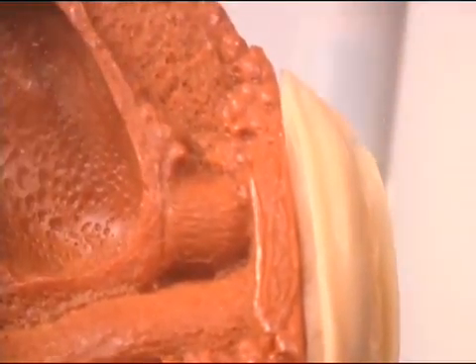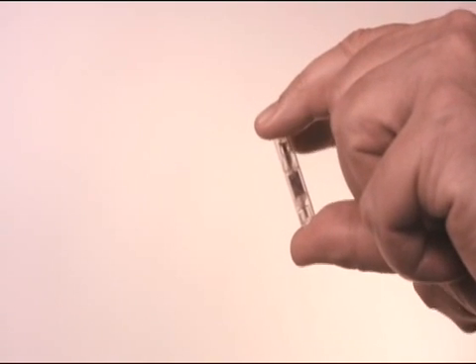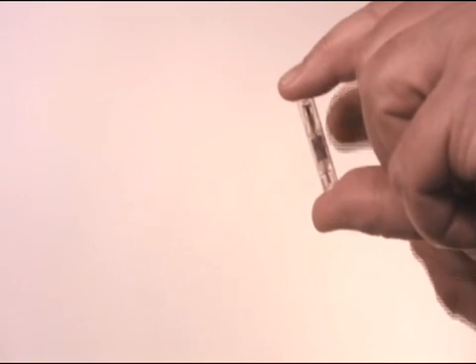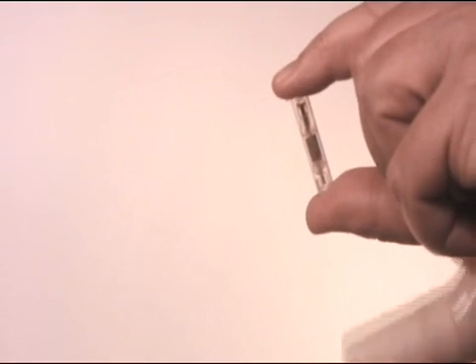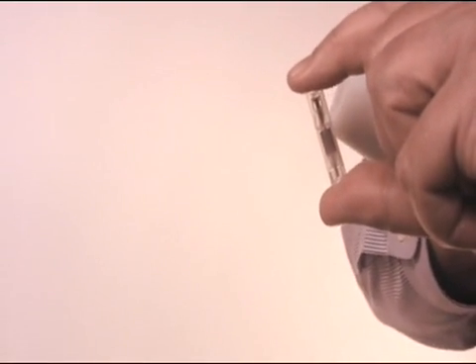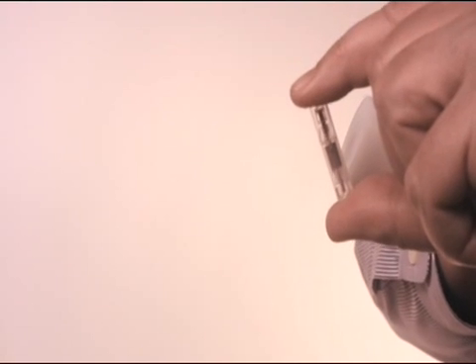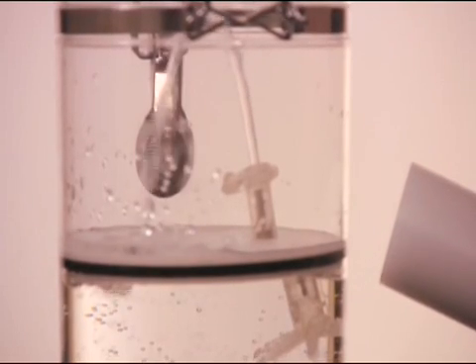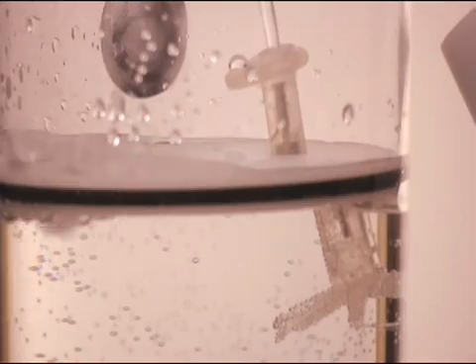Inside the inflow is a small magnet. Attached to this magnet are plastic rotors, top and bottom. When this magnet is spun by the remote control, the effect is to create a turbine pump spinning at 10,000 RPM. The effect is to create an almost normal flow rate and to fully evacuate the bladder.